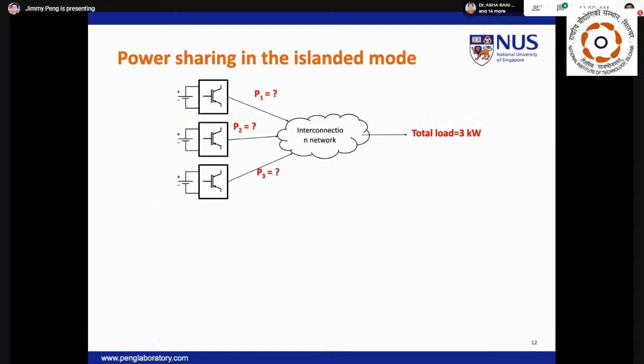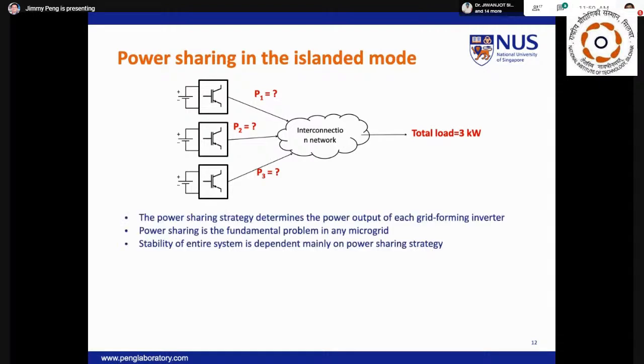A more important question is how should each inverter determine its power output to share the total load? This leads to an important research topic of power sharing among inverters. In fact, inadequate power sharing will cause some inverters to overload or be unable to regulate the voltage and frequency in an event of a disturbance. Therefore, the stability of a microgrid is dependent on the power sharing strategy adopted by the inverters.